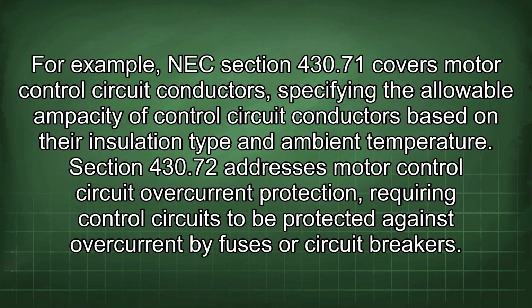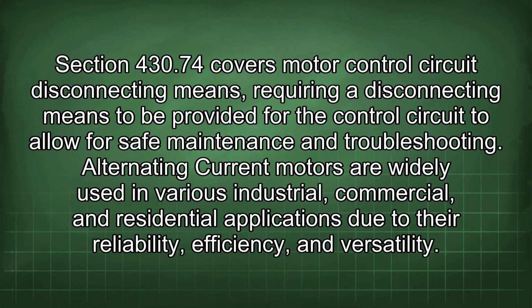For example, NEC Section 430.71 covers motor control circuit conductors, specifying the allowable ampacity of control circuit conductors based on their insulation type and ambient temperature. Section 430.72 addresses motor control circuit overcurrent protection, requiring control circuits to be protected against overcurrent by fuses or circuit breakers. Section 430.74 covers motor control circuit disconnecting means, requiring a disconnecting means to be provided for the control circuit to allow for safe maintenance and troubleshooting.